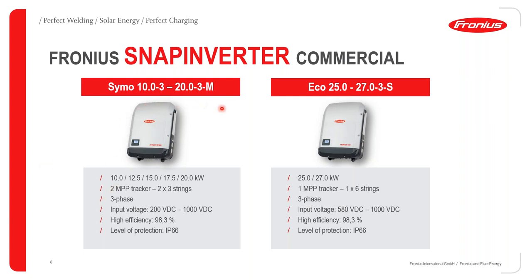Our commercial range starts with the Symo 10 to 20 kilowatts three-phase inverter, with two MPP trackers supporting three strings per tracker at 1000V DC, input voltage 200V to 1000V DC, efficiency 98.3%, and IP66 protection. The Fronius Eco comes in 25 or 27 kilowatt variants, three-phase, one MPP tracker with up to six strings, input voltage 580V to 1000V DC, efficiency 98.3%, IP66. All four inverters are compatible with our PV genset solution — easy, advanced, or professional.